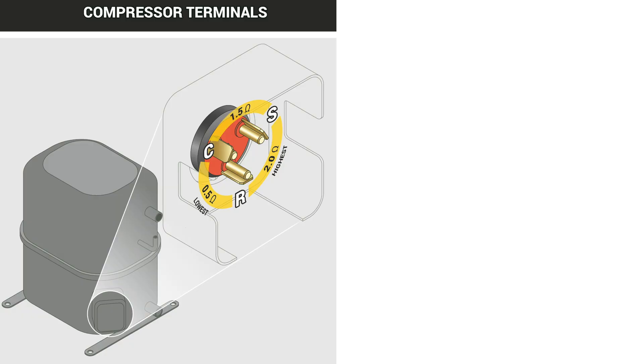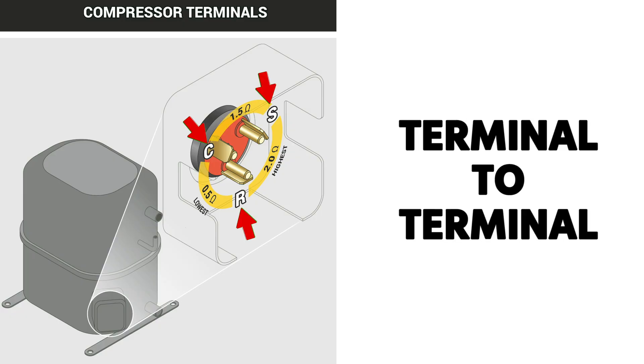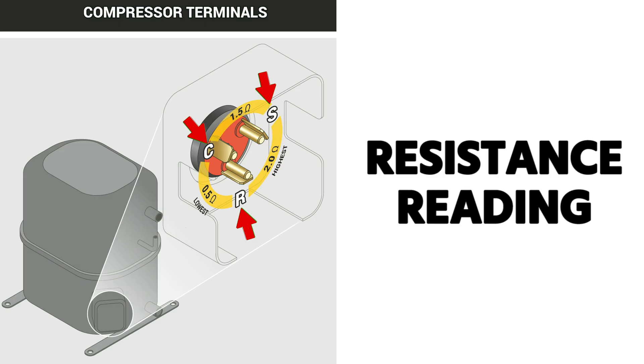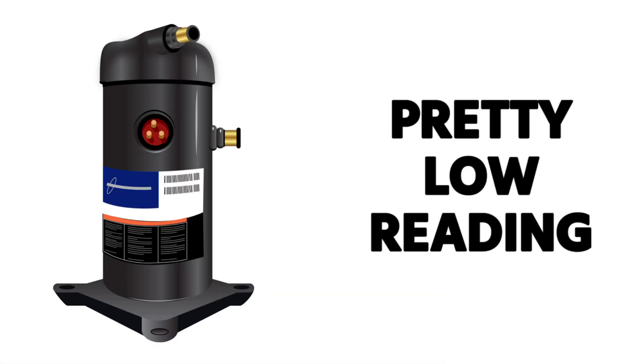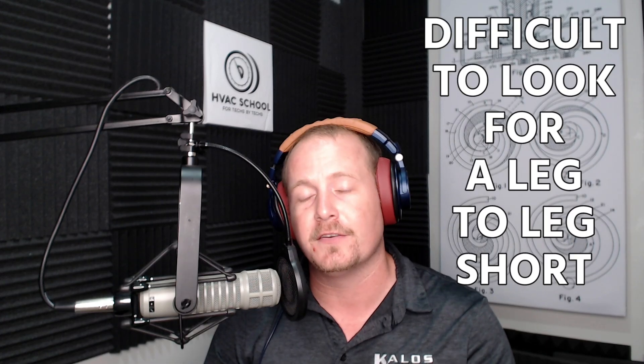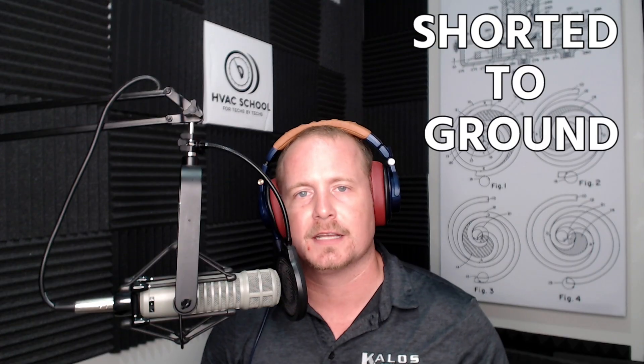Just to talk briefly about this in terms of a compressor — on a typical single phase compressor you have your common, your start, and your run. If we're measuring for an open, we measure from terminal to terminal and we see if we have continuity or if we have a resistance reading in between all of them. Generally on compressors that's going to be a pretty low reading. If you want to check for a short, then you take each terminal and you measure to ground. It's very difficult to look for a leg-to-leg short. A shorted leg-to-leg is actually pretty rare. It can happen, but more often than not it's going to be shorted to ground.